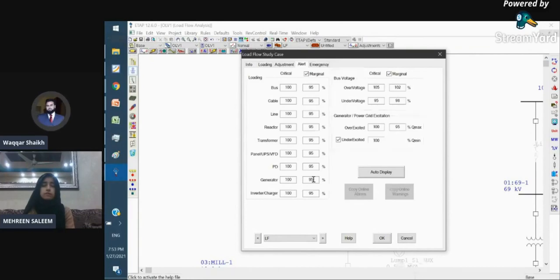The second type of problem is the overexcitation condition. This happens if there is excess reactive power demand from the network. If the generator has a capability limit allowing 100 kVAR to be delivered, but you try to draw more than that, it will cause overexcitation, triggering another type of alarm. You then have to reduce the load so that it operates within the generator's capability curve.